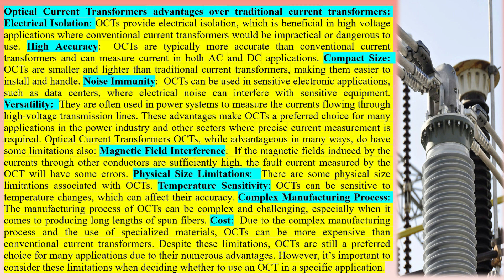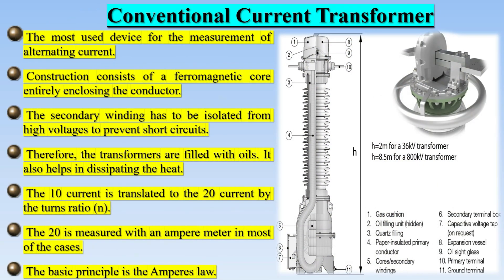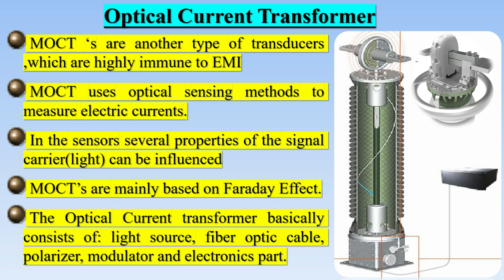Optical current transformers have several advantages over traditional current transformers. Electrical Isolation: OCTs provide electrical isolation, beneficial in high-voltage applications where conventional transformers would be impractical or dangerous. High Accuracy: OCTs are typically more accurate and can measure current in both AC and DC applications. Compact Size: OCTs are smaller and lighter, making them easier to install and handle. Noise Immunity: OCTs can be used in sensitive electronic applications such as data centers. Versatility: They are often used in power systems to measure currents through high-voltage transmission lines. These advantages make OCTs a preferred choice for many applications in the power industry where precise current measurement is required.